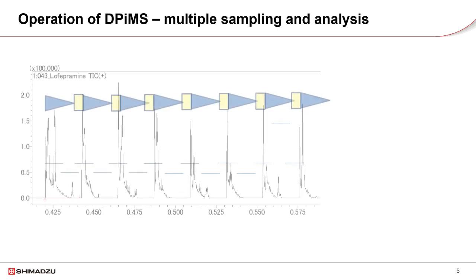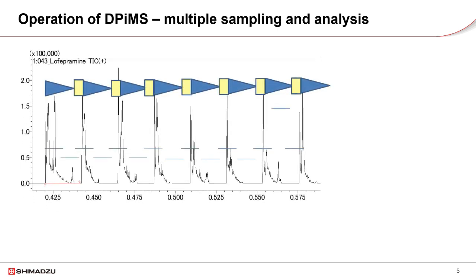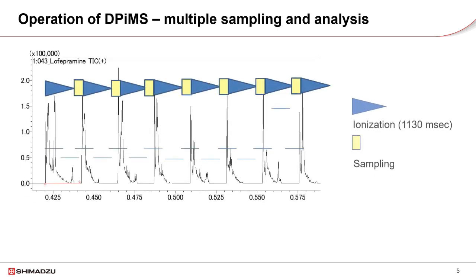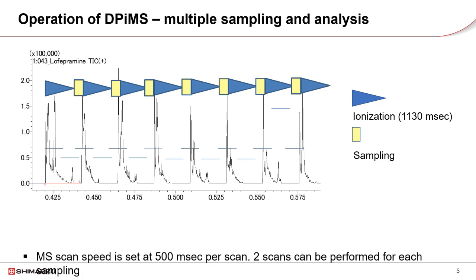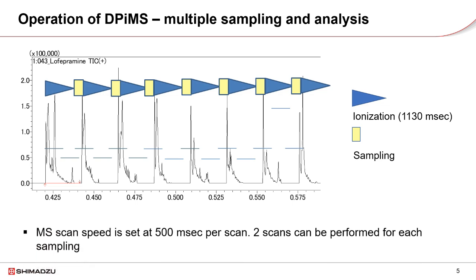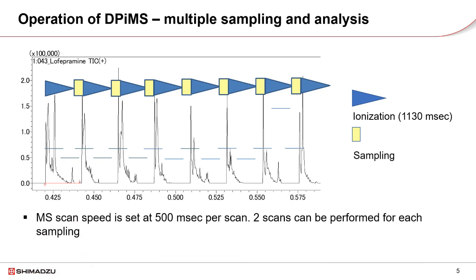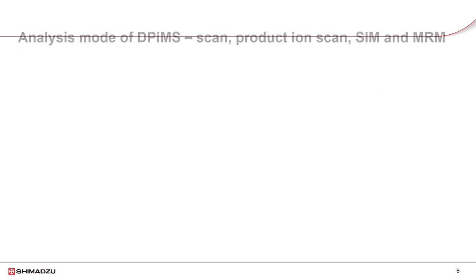The ionization time for each sampling is 1,130 milliseconds. If the MS scan speed is 500 milliseconds per scan, we can obtain two spectra for every sampling. Multiple sampling and analysis are the standard operation mode for DPI-MS.